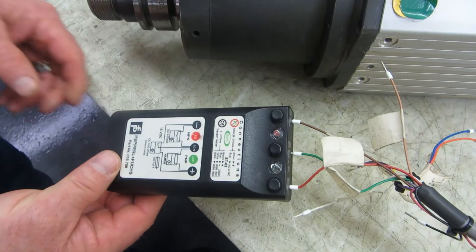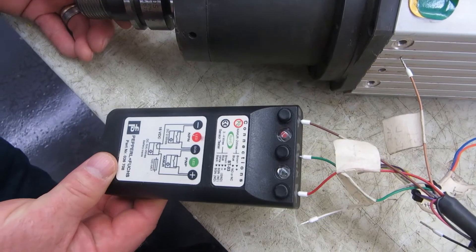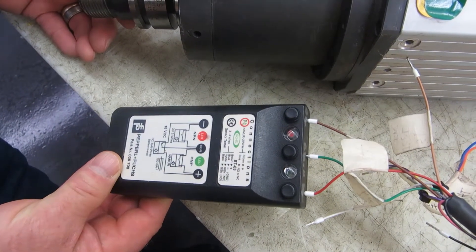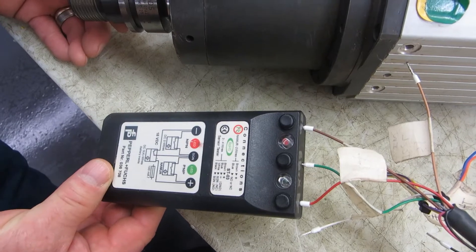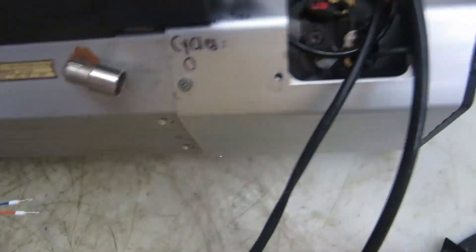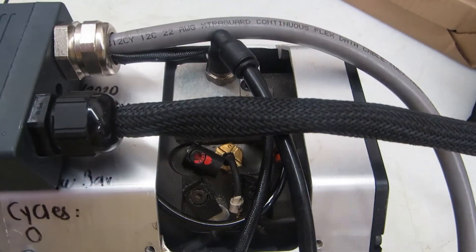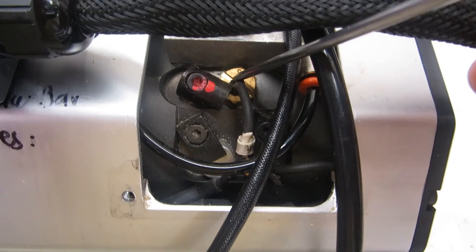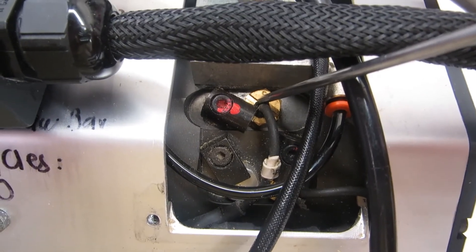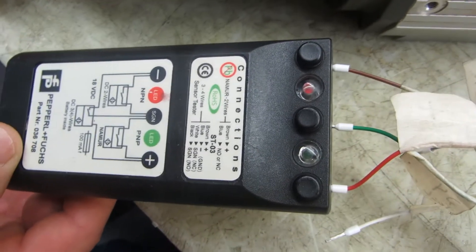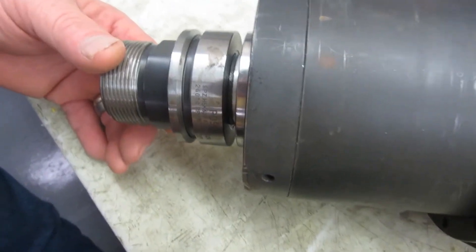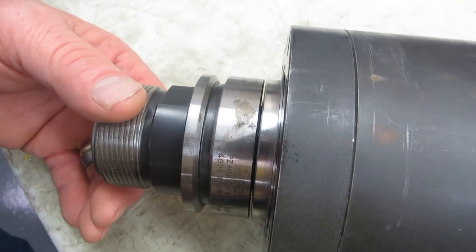To confirm that tool lock is working correctly, sensors S4 and S1 need to be set properly. S4 will be the one that you set first. S4 is this sensor on top, right here. So you'll have your meter set up to check S4. Then go ahead and place a tool holder in the tool clamping.